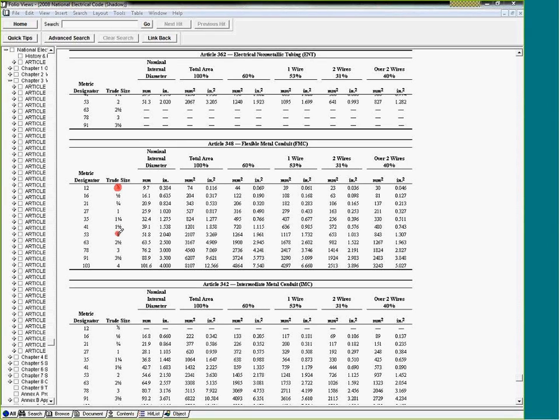So say we have a 2 inch, and let's say I'm filling 40%, which is more than 2 conductors. Then the conductor area I can fill is only 1.307. For 24 inches or less, I can fill up to 60%, and that takes me all the way up to 1.961, only if the conduit is 24 inches or less. Guys, let me see if anybody has any questions. Any questions? Make sure I did not put you to sleep.